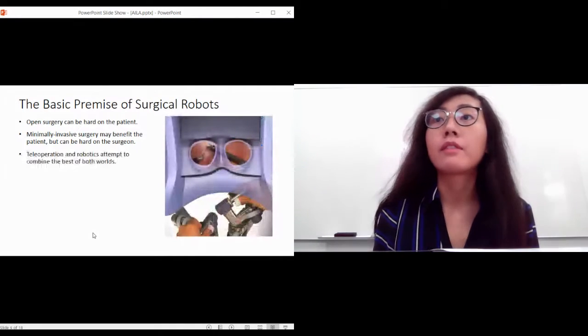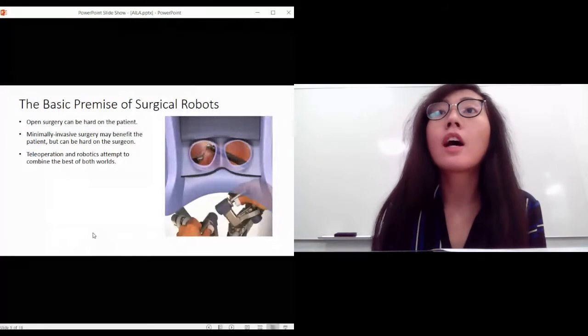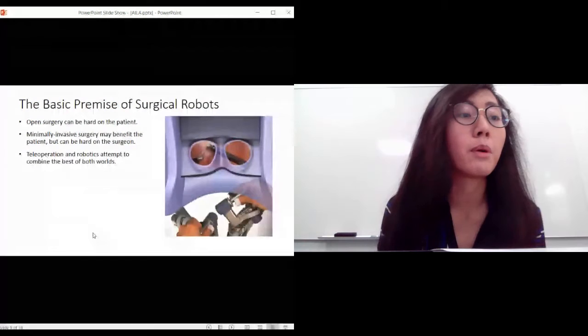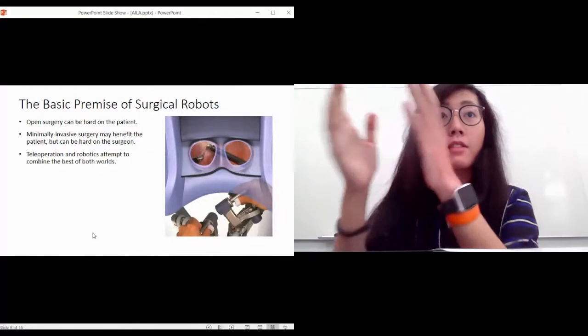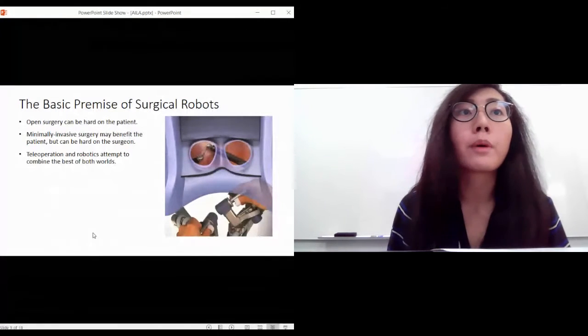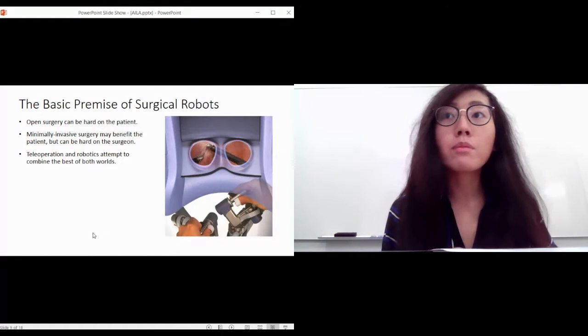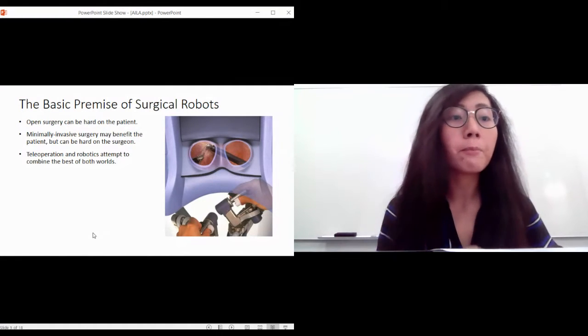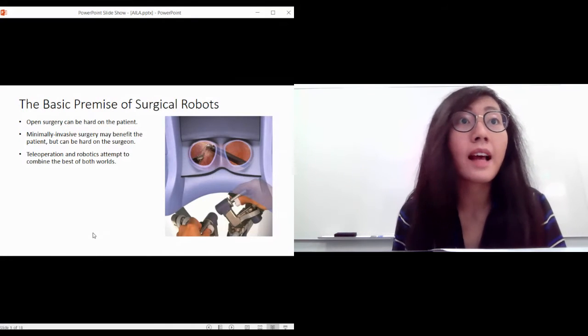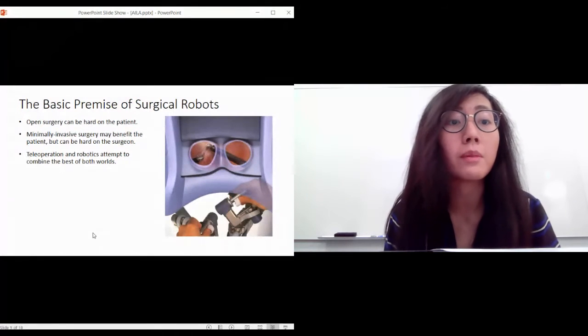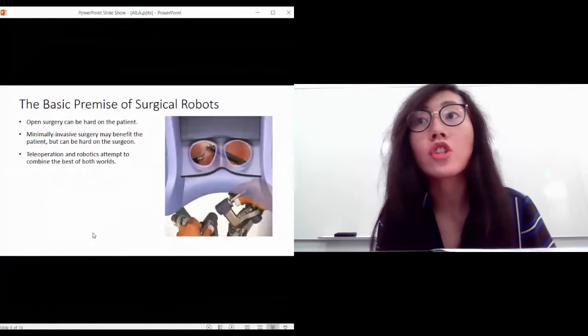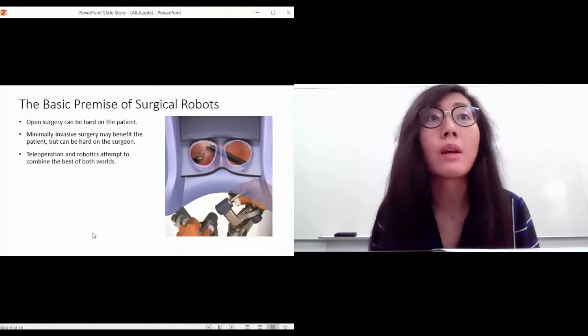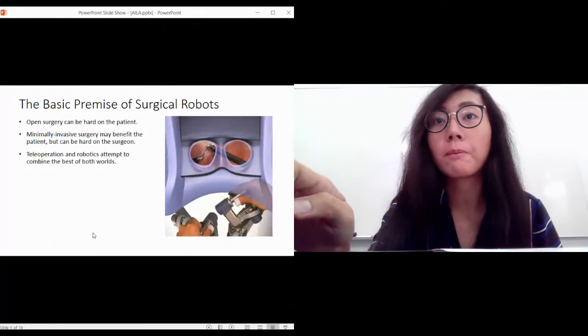Now surgical robots, for example Da Vinci, use teleoperation, which attempts to combine the best of both worlds. Based on teleoperation, the surgeon sits at the surgeon console which is separated from the patient side robot and looks at the endoscopic view from a headset or console and performs the surgery using two master manipulators, one on each hand. The gestures are then mimicked exactly by robots on the patient side. This is how surgical robots can help by making the gestures intuitive - the surgeon can move the same way they want to go while also having that minimally invasive technique and benefits for the patient.